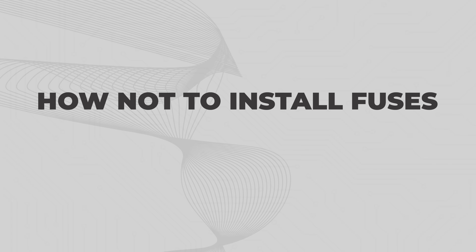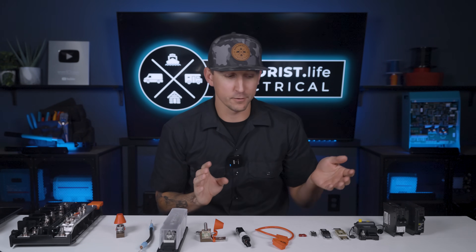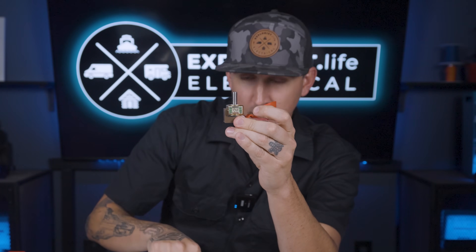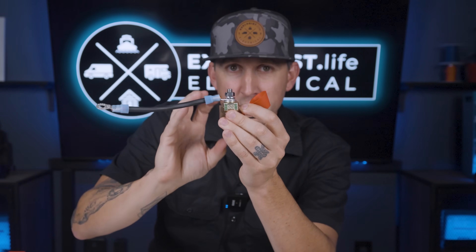How not to install fuses. The main problem that we see here at Explorist.life, whether it's with in-person electrical system checks at events, or whether it's our email support inbox for shop.explorist.life, the biggest problem without a doubt is whenever somebody installs a fuse onto a fuse holder, and then puts a washer, and then puts their wire lug, and then puts their lock washer and nut, tightens it all down, and they think they're good to go.